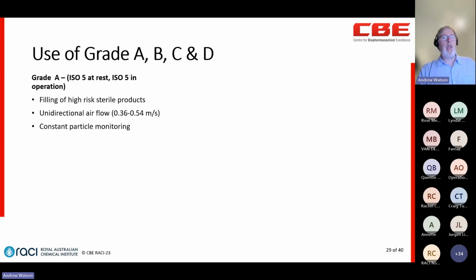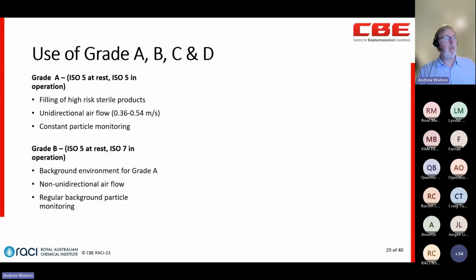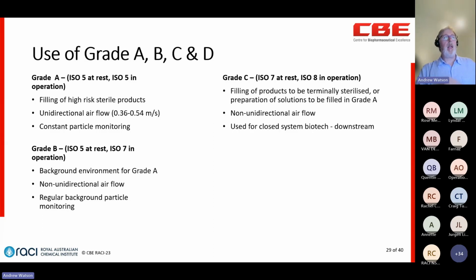So if we just quickly go over the difference between grade A, B, C, and D. Grade A is used for the filling of high-risk sterile products. Grade B is the background to grade A. So if you've got a biological safety cabinet or a clean air workstation where you're preparing sterile materials, you'll have a grade B background where the personnel will actually stand. Grade C is for filling of products that are going to be terminally sterilised or in preparation of solutions that are later going to be filled in grade A.